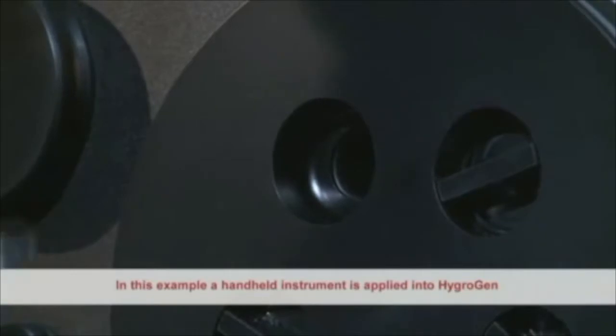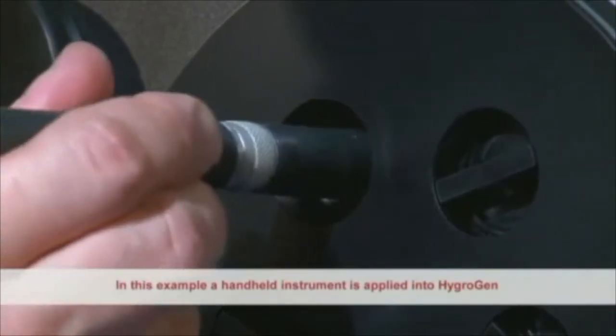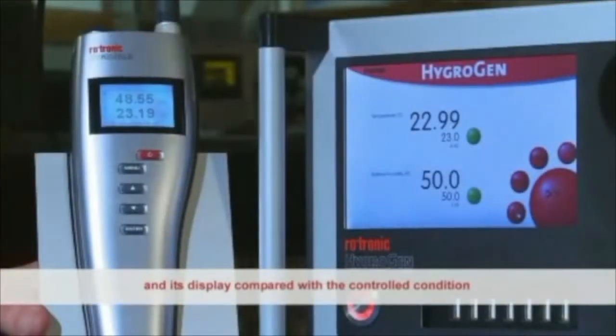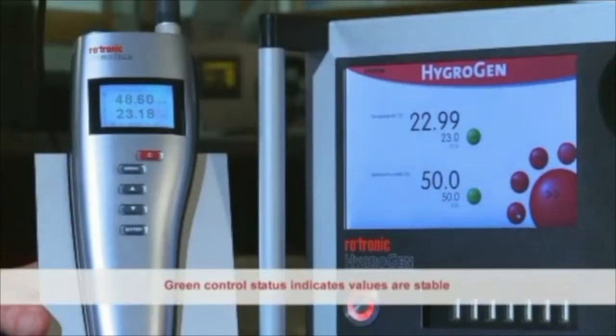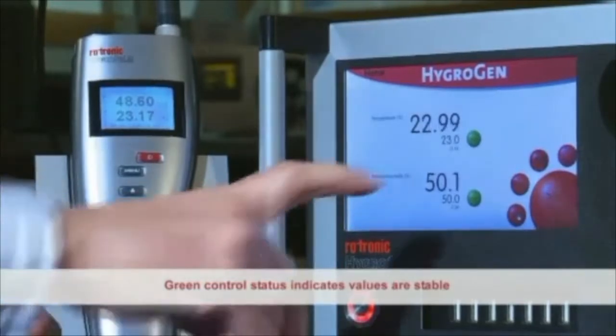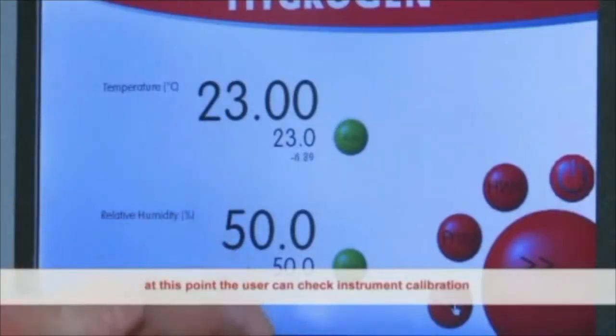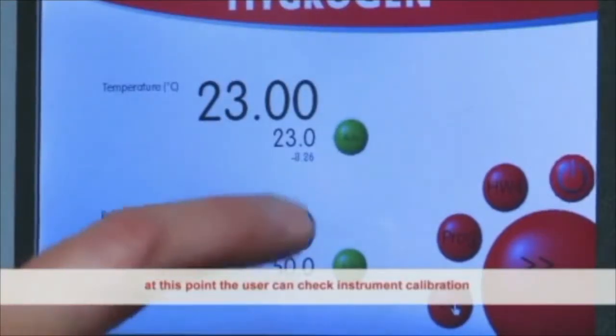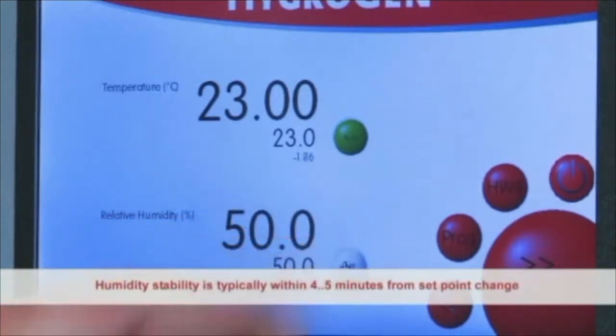In this example, a handheld instrument is applied into the HygroGen and its display compared with the control condition. Green control status indicates values are stable. At this point, the user can check instrument calibration. Humidity stability is typically within 4 to 5 minutes from a set point change.